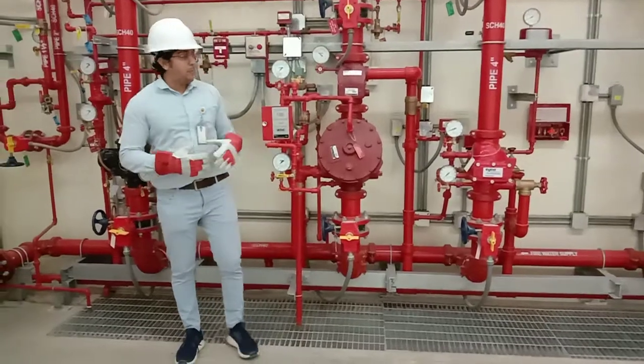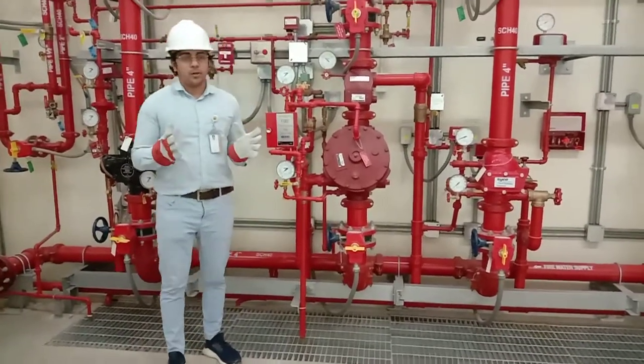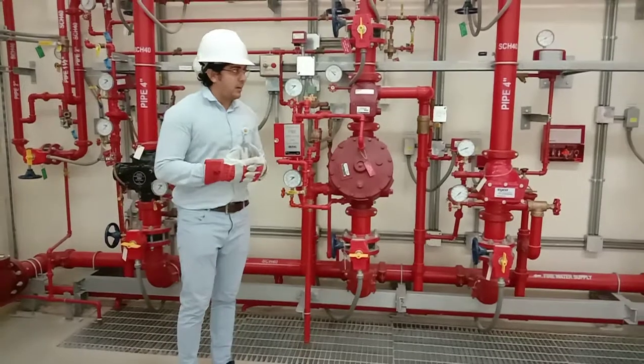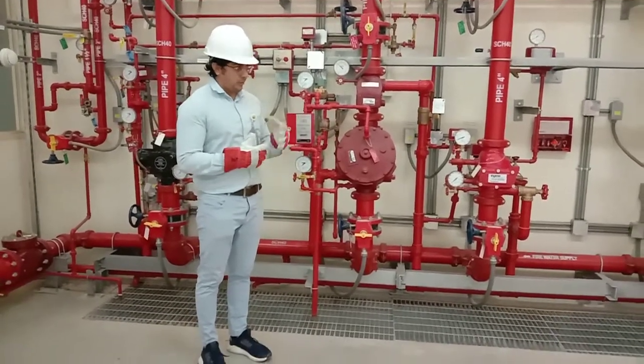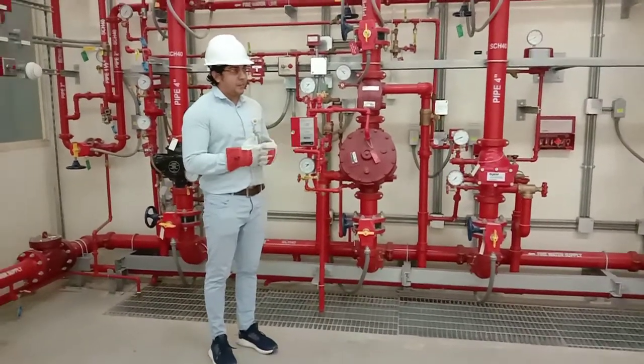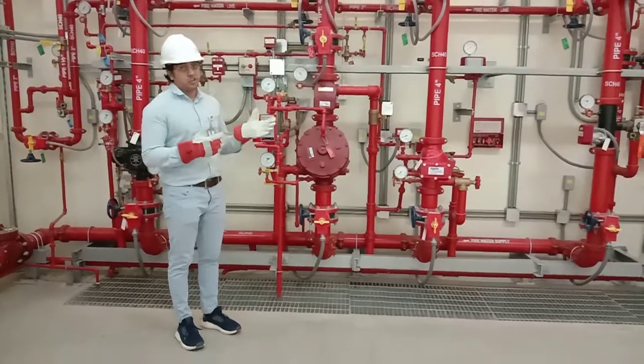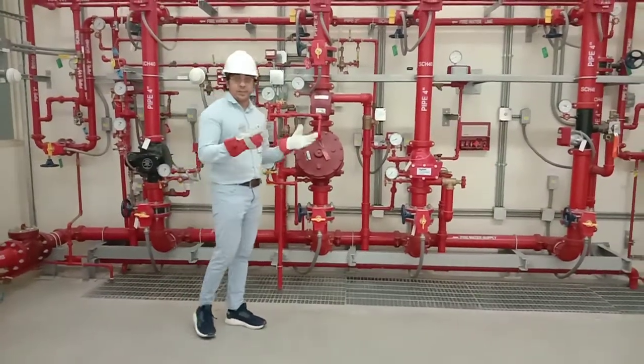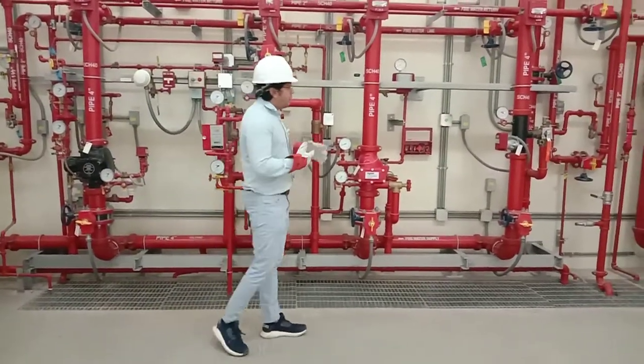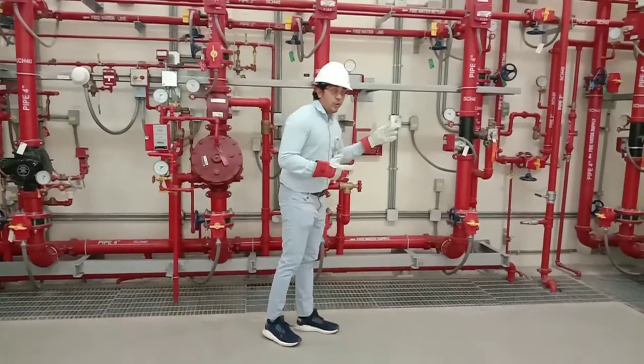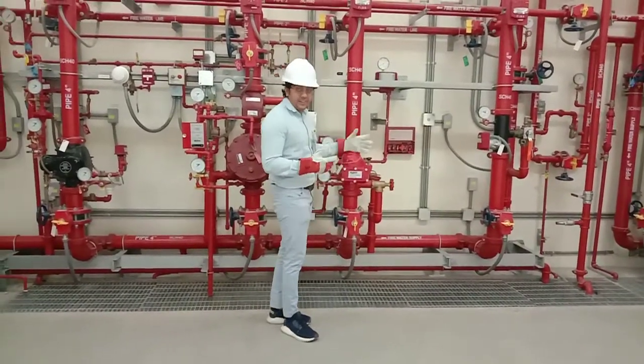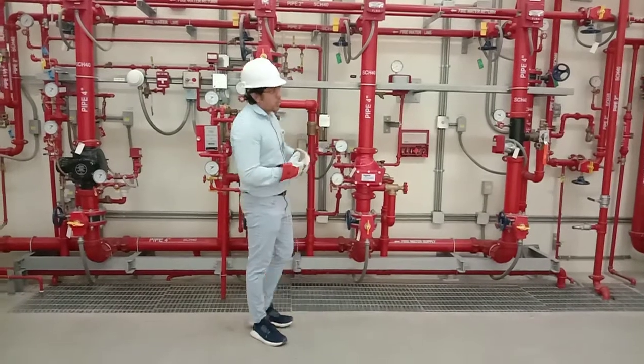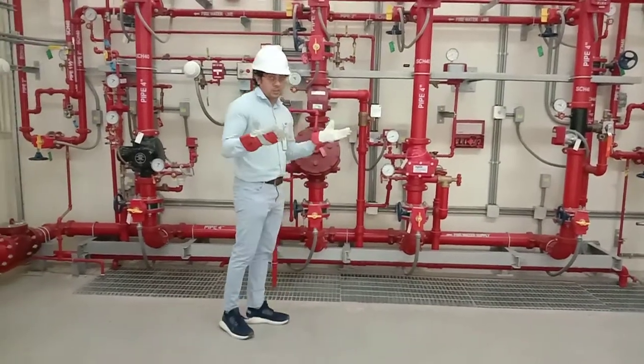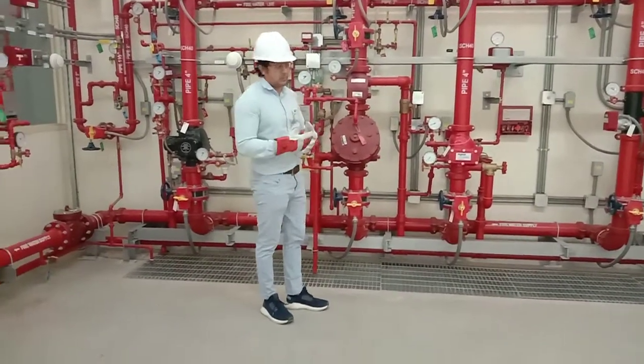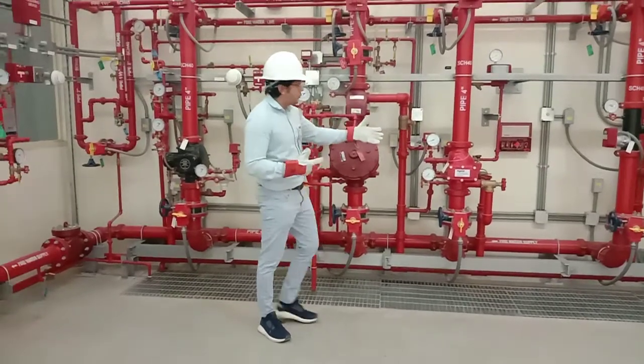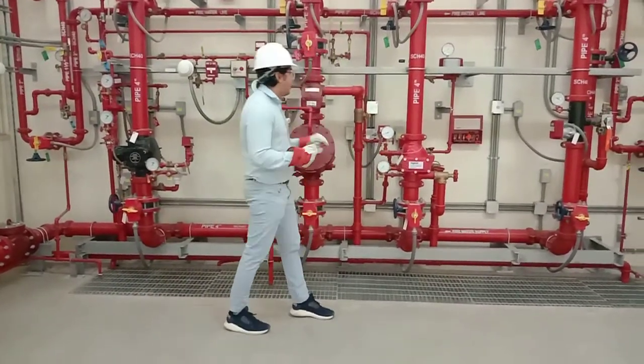We have the pre-action system, the double interlock pre-action system. We discussed the wet pipe system, right? We use it in areas where there is no chance of freezing. It is the most common application worldwide, 80 to 85% are installing it. But it fails at locations where we have freezing temperature or a freezing atmosphere, normally in regions where the temperature is always below -6, right? So in those areas we have to use the dry pipe system.